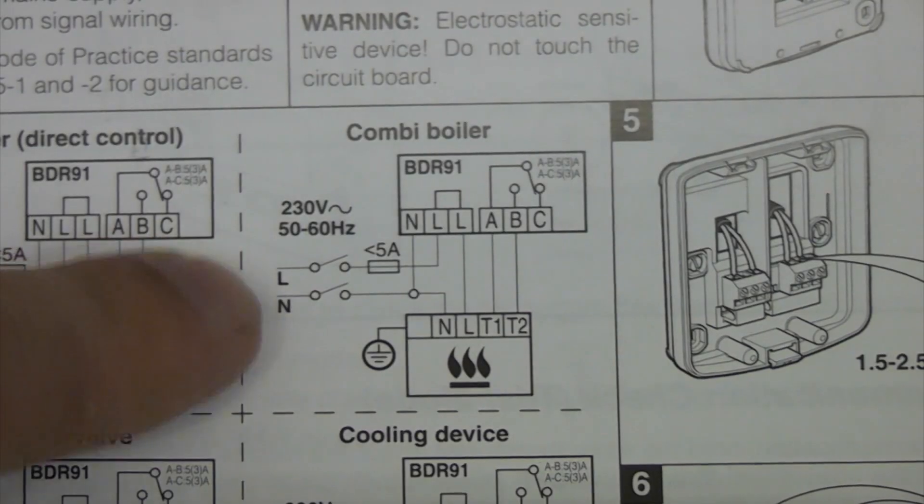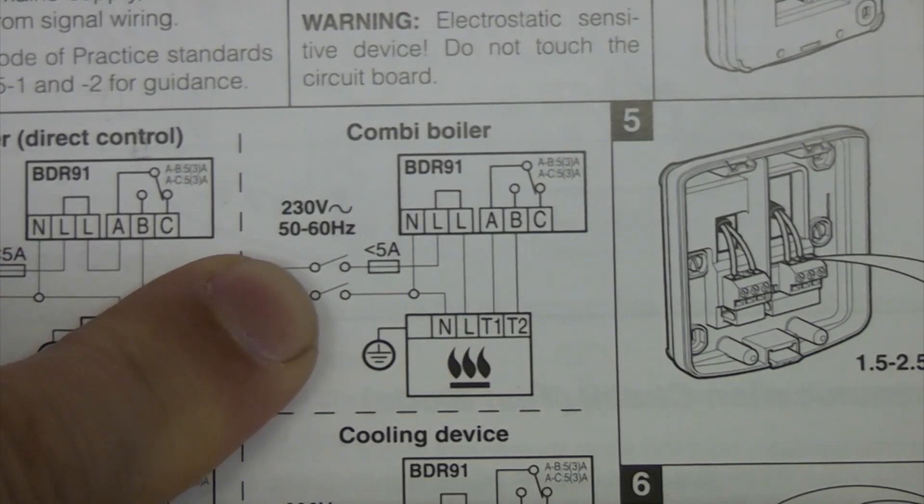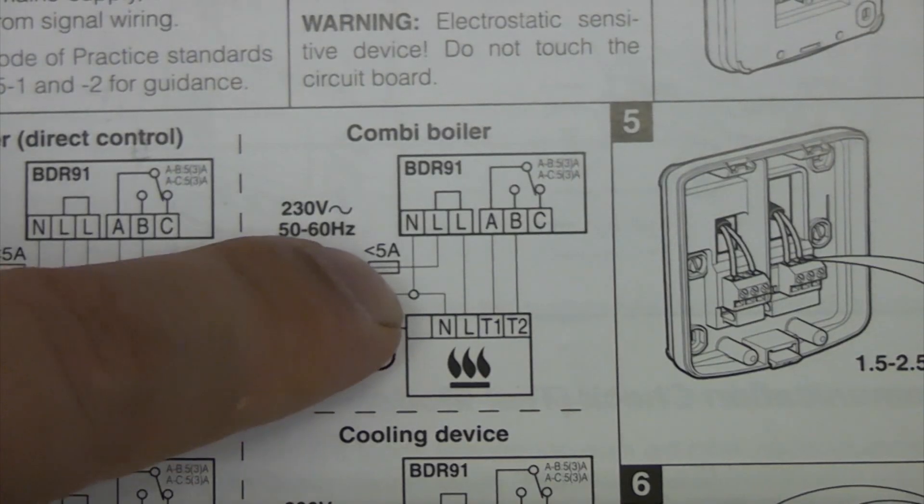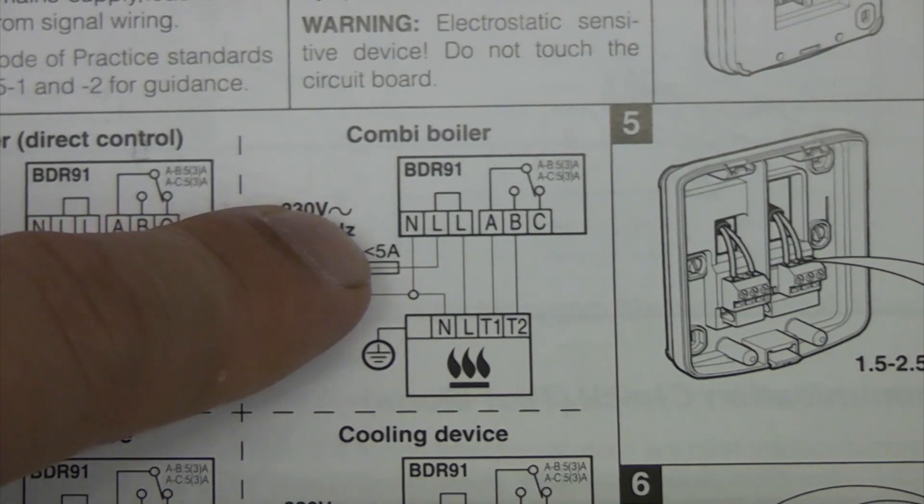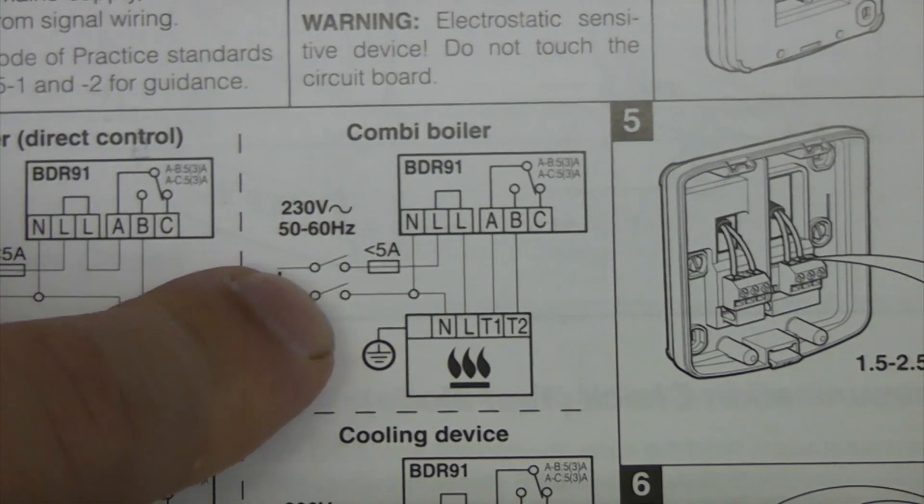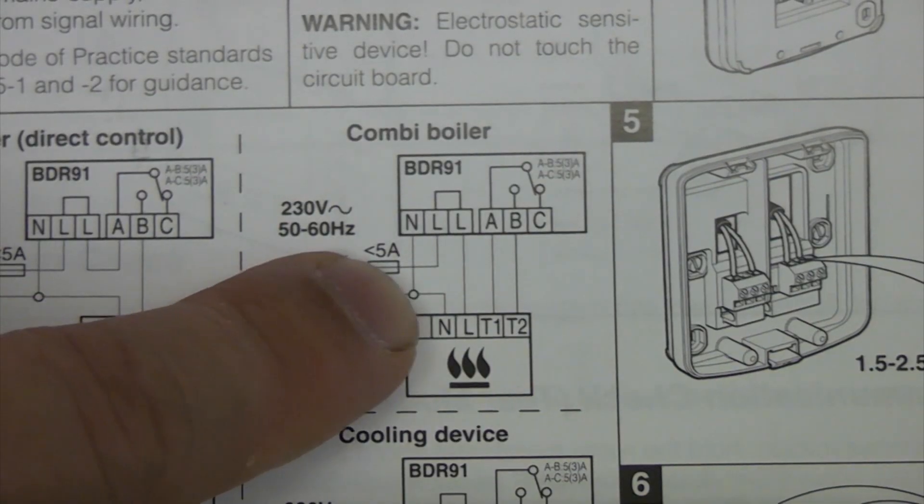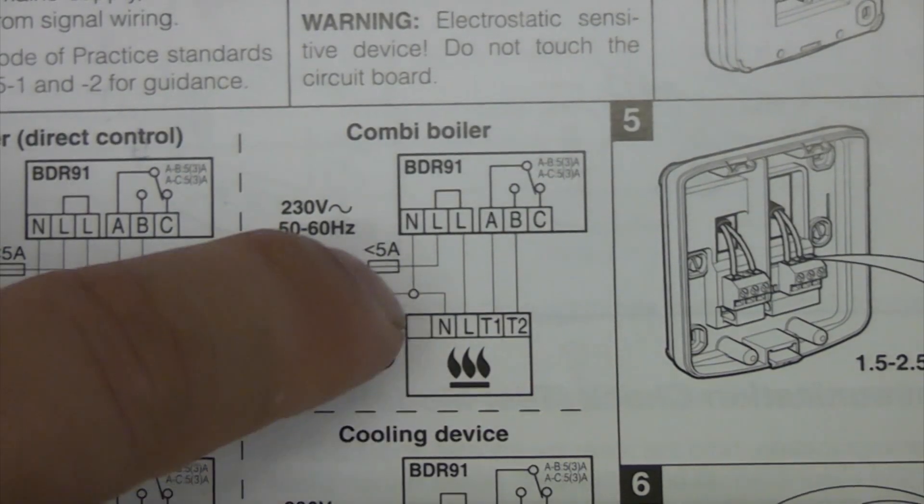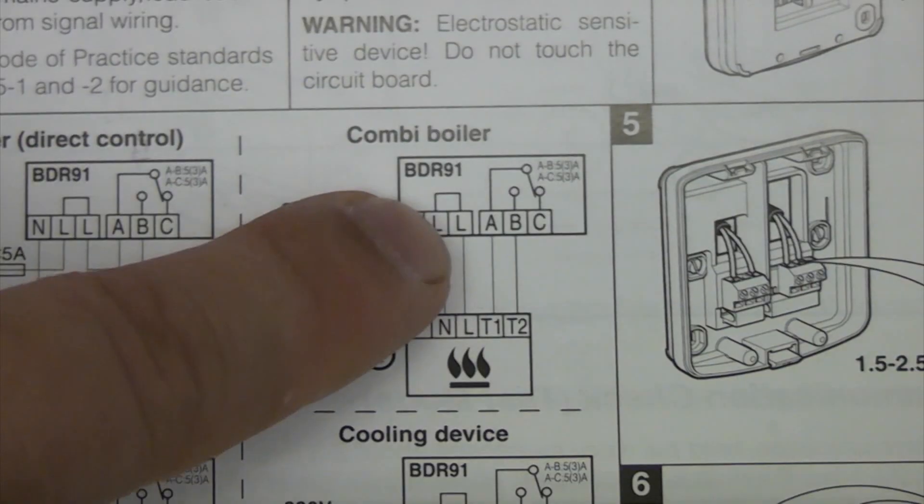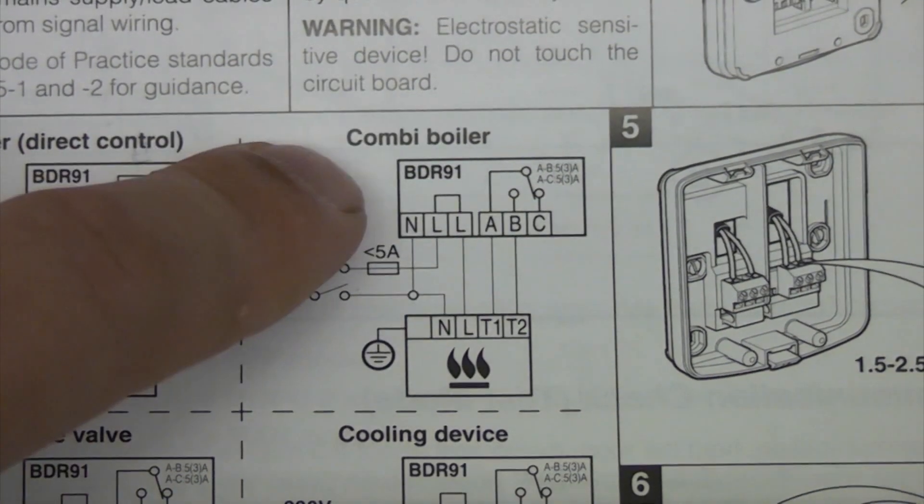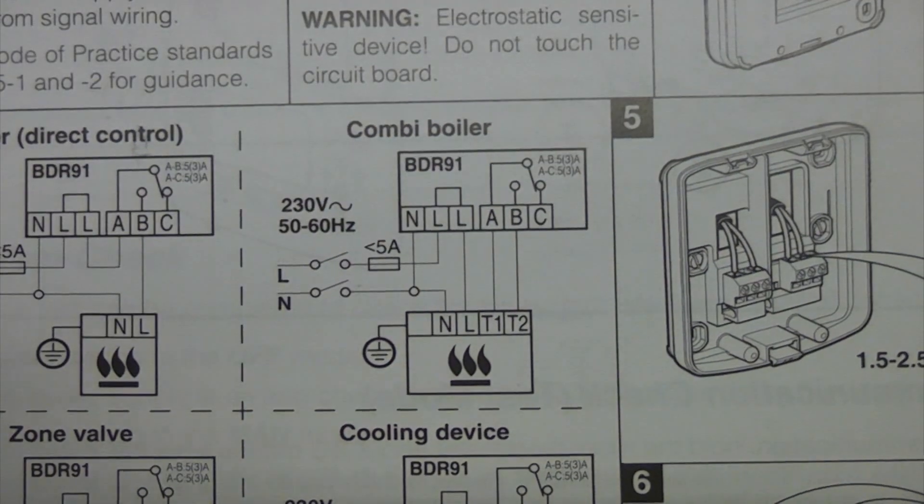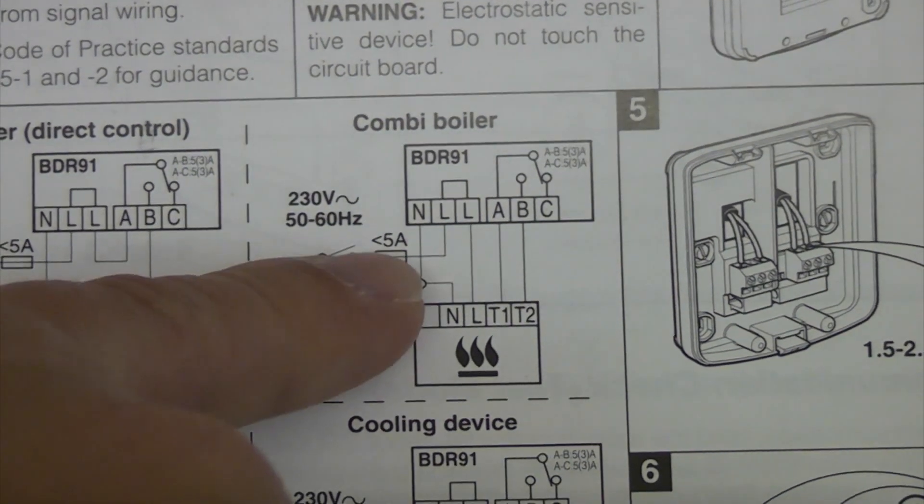So we need a live and a neutral which goes through a double pole switch and then a fuse that is smaller than 5 amps, and then all we need to do is take a connection to the neutral and a connection to the live. And what we are going to do is we are just going to piggyback those connections from the connections that are already on the boiler because they already go through a double pole switch and the fuse.